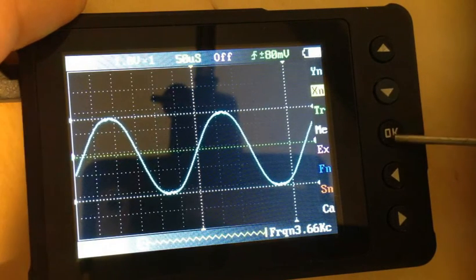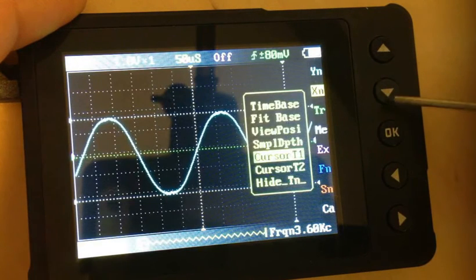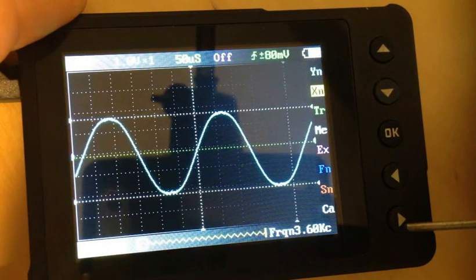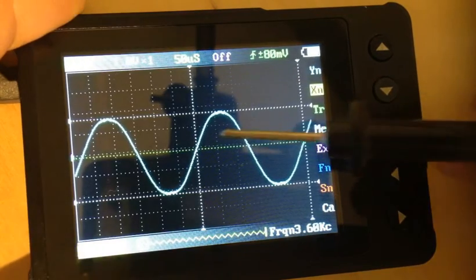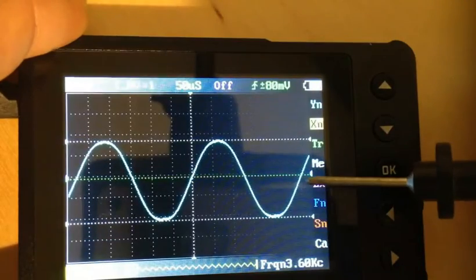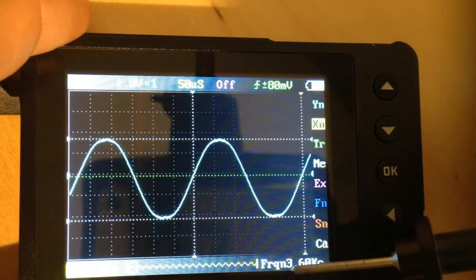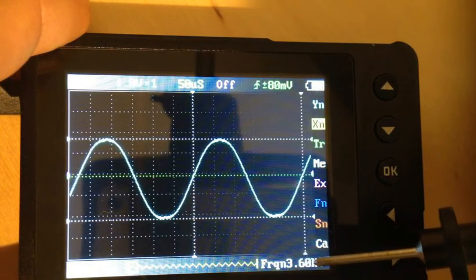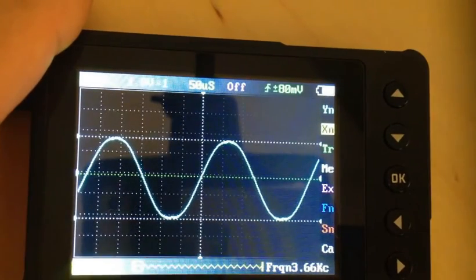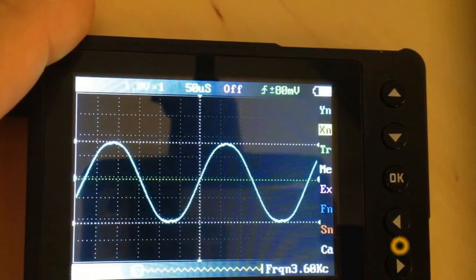And we'll go to cursor T2, and we're going to move it until it's one cycle. So from that cursor to that cursor, we can now see 278 microseconds. A fellow could invert this and get the frequency, but conveniently the frequency is already displayed here: 3.60 kilohertz. There you go. That's how you use the cursors to make simple measurements.